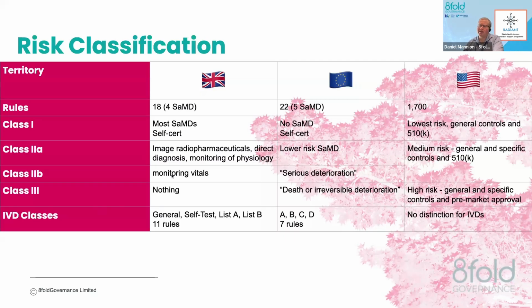Class 2B in the UK is for monitoring vital physiological parameters, and the EU defines it as software that could cause serious deterioration of the health of the patient. Class 3 in the UK, you can't be class 3 if you're a software medical device in the UK. The rules don't allow for it. Class 2B is as high as you can get. In the EU, if your software could cause death or irreversible deterioration of the patient, you'd fall into class 3.